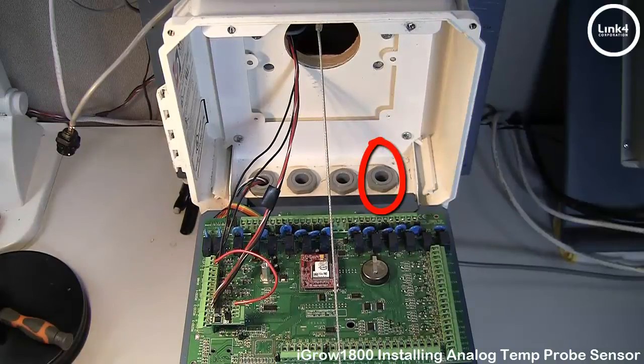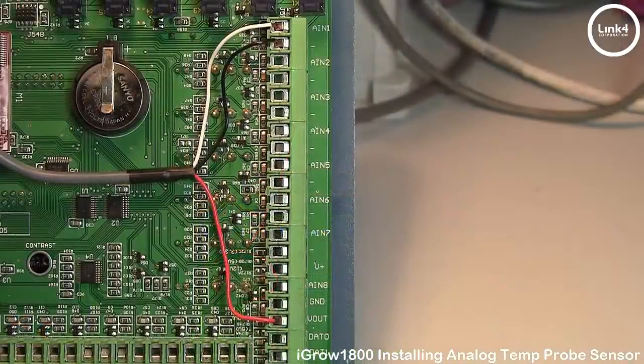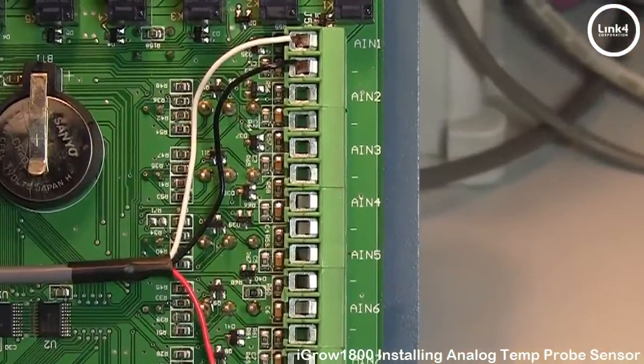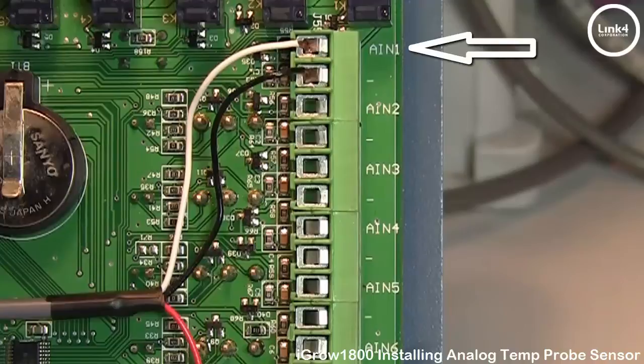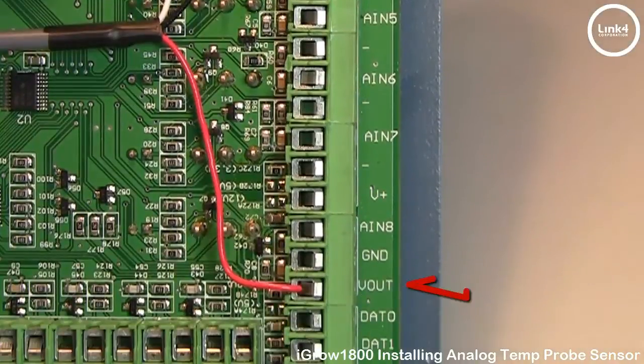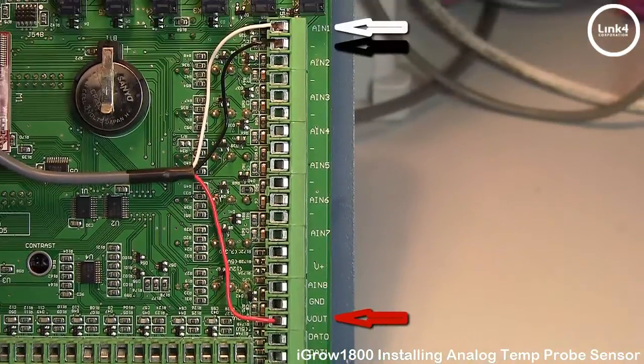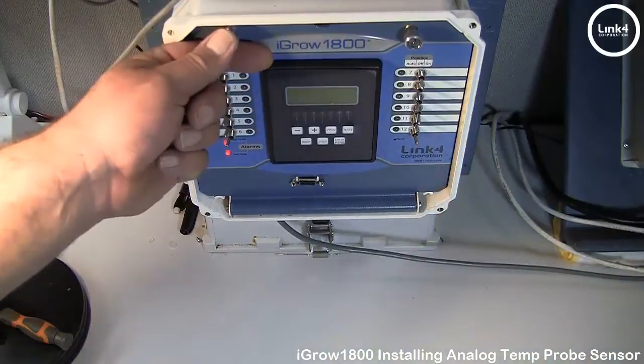You will land the wires on the following terminal block locations. And for our example, we're going to use AIN1. You will land the white wire to AIN1, the black wire to the negative of AIN1, and the red wire to the V out. Once you have landed your wires, simply close the controller and power the unit back up.